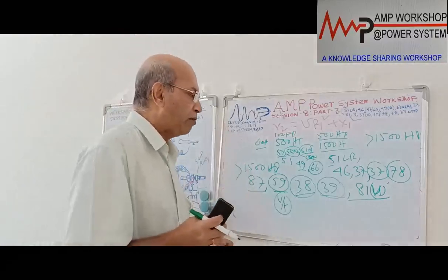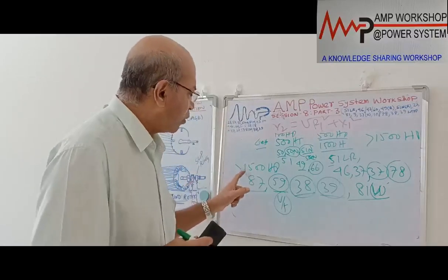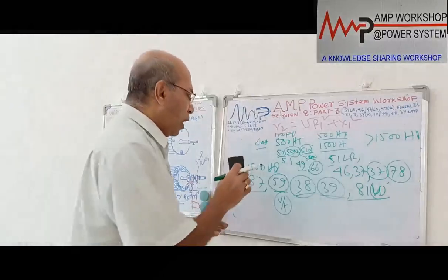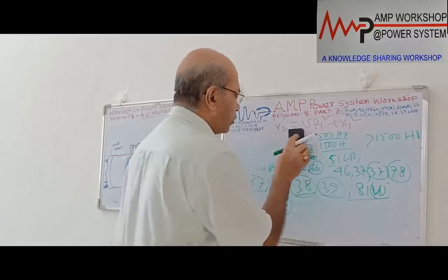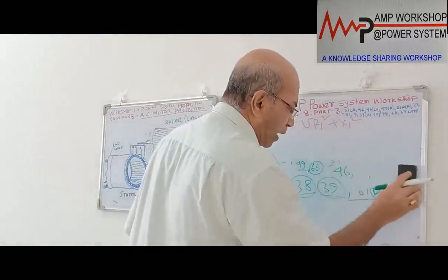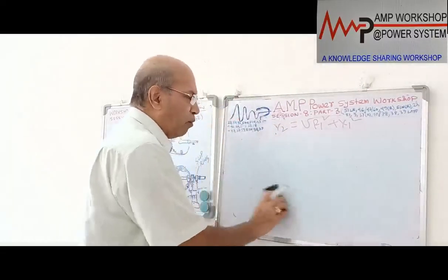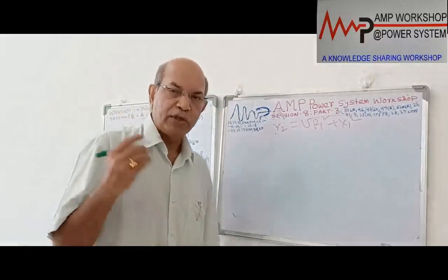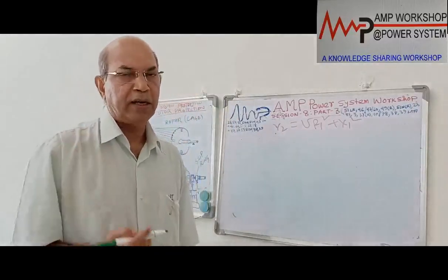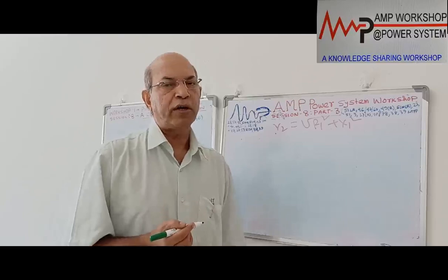On the last point I want to discuss, for this size of motor, 1500 HP and bigger, this motor is normally not an air cooled motor. These motors are not naturally air cooled; either there is forced air cooling or water cooling. And if the motor is located in a hazardous area, obviously the motor will be a water cooled motor.